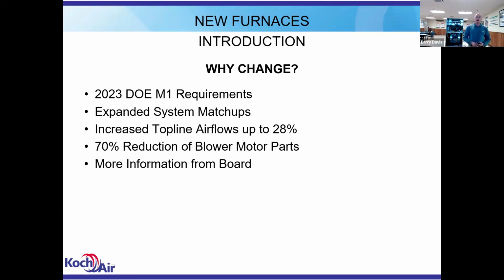Okay. And a lot of that had to do with the energy used by the blower. The current product line with the control board did not meet that minimum guideline, so they had to make some changes. They had to do some improvements. Carrier Bryant decided, hey, if we got to make improvements anyway, let's make improvements on some other areas that we've been trying to do. So that's where they came up with a higher speed motor in this new board with the near field communication, taking advantage of new technology.